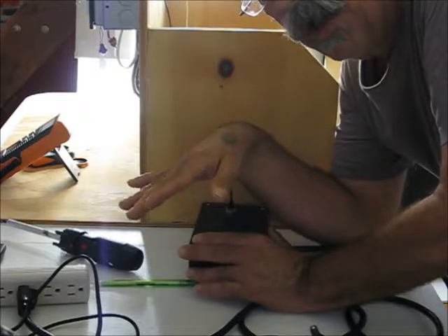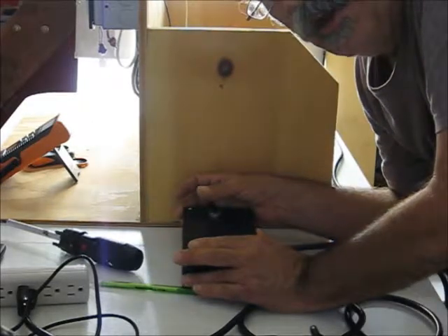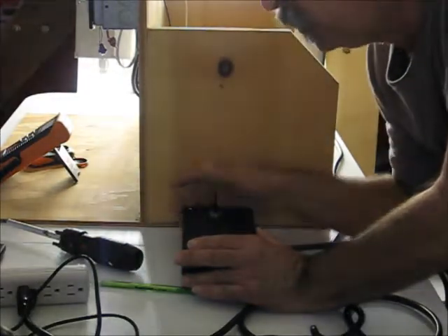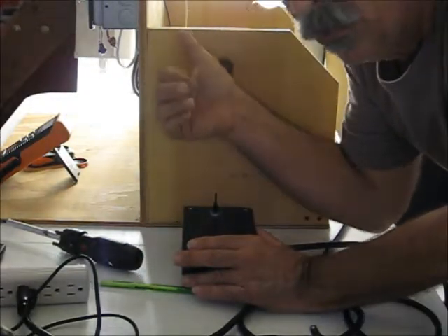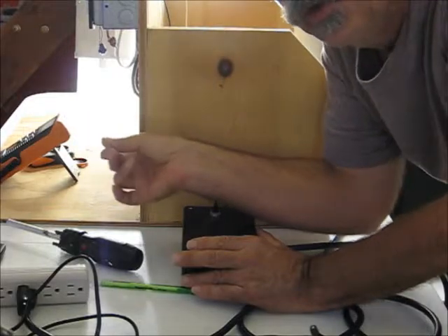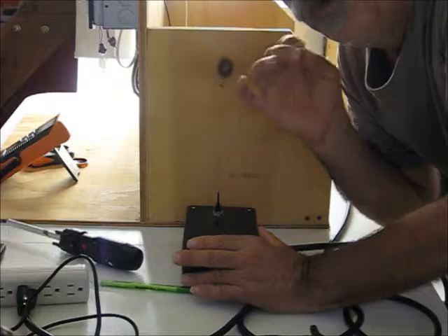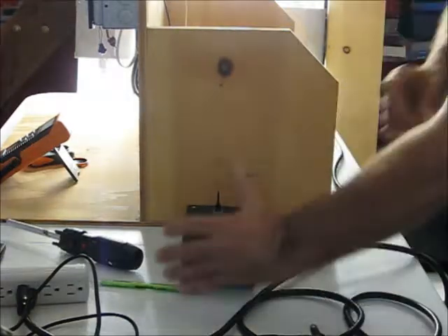I'm going to kill all the lighting. I'm going to vary the controlled sunlight up and down, and we'll take the ratio between the system sensor and our task location and get our sensor ratio at varying levels of daylight illumination.